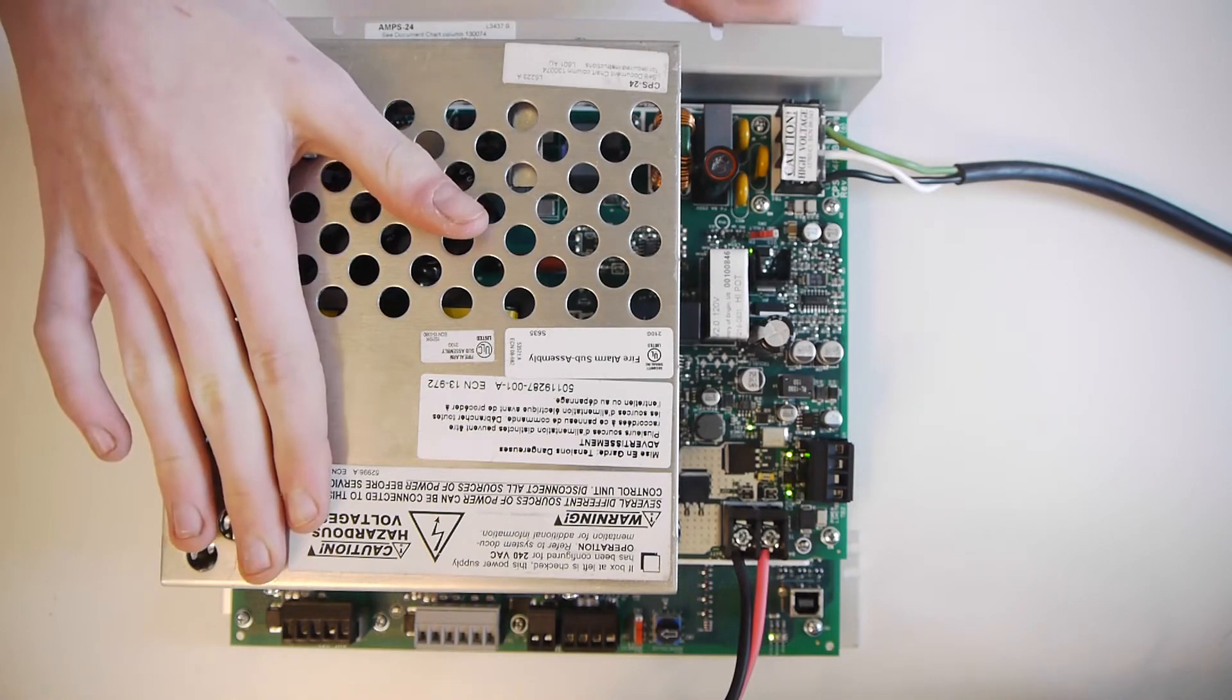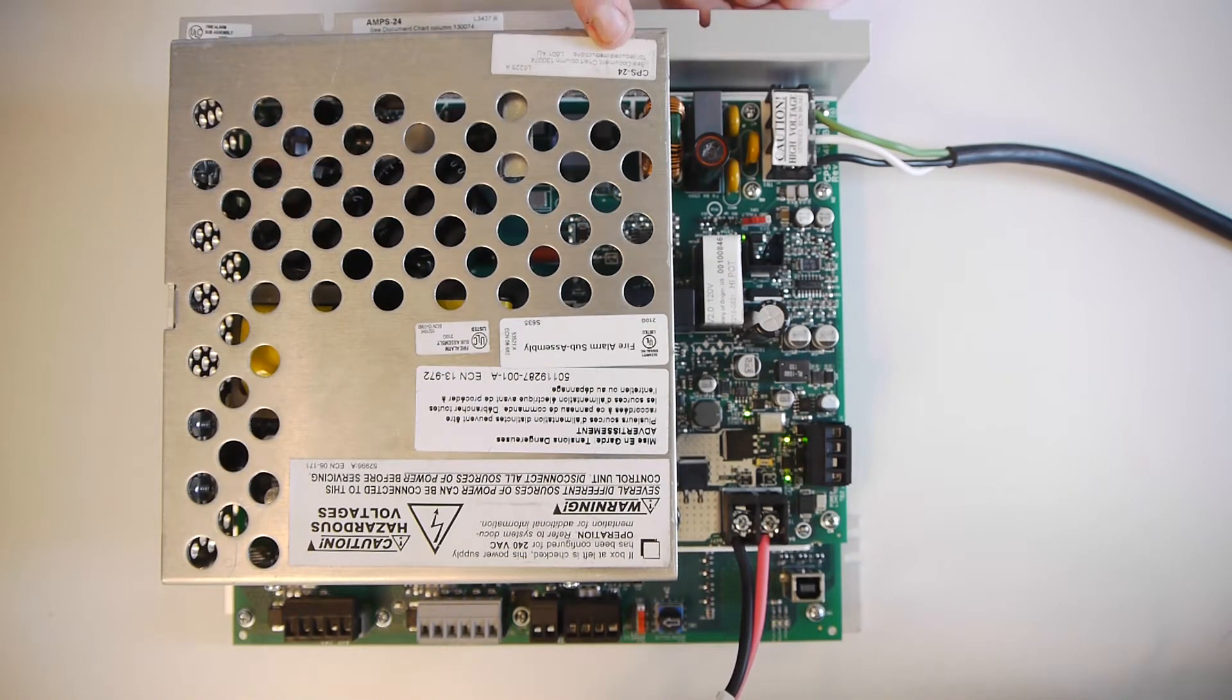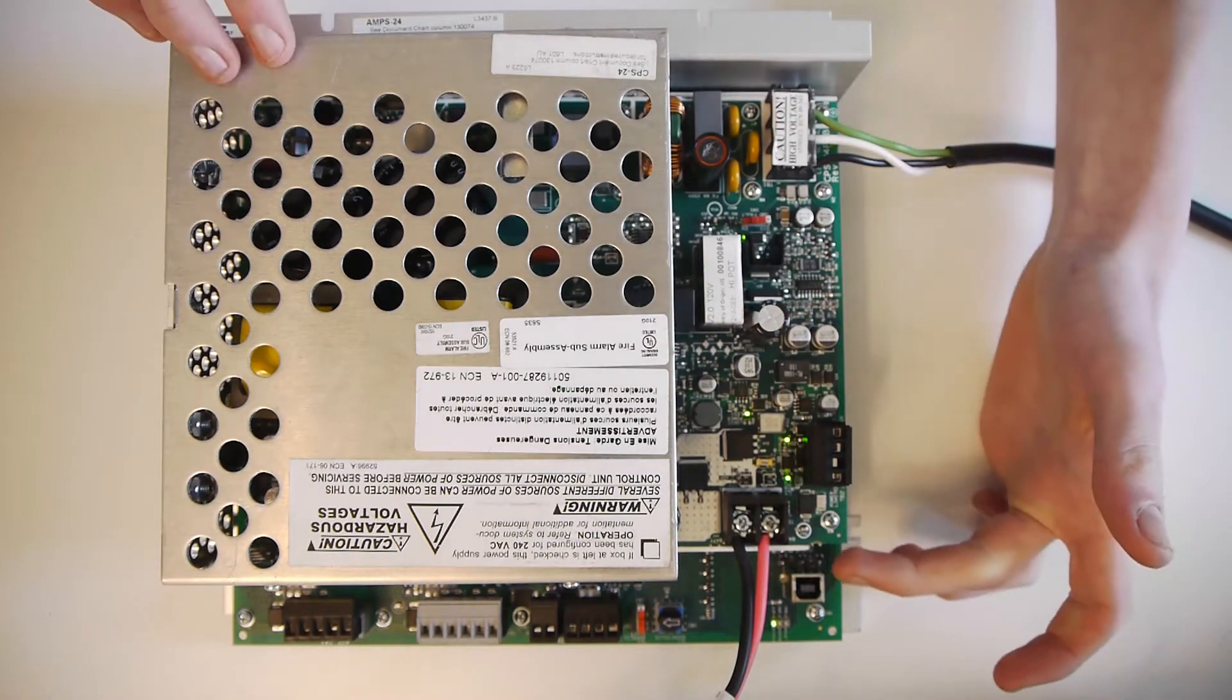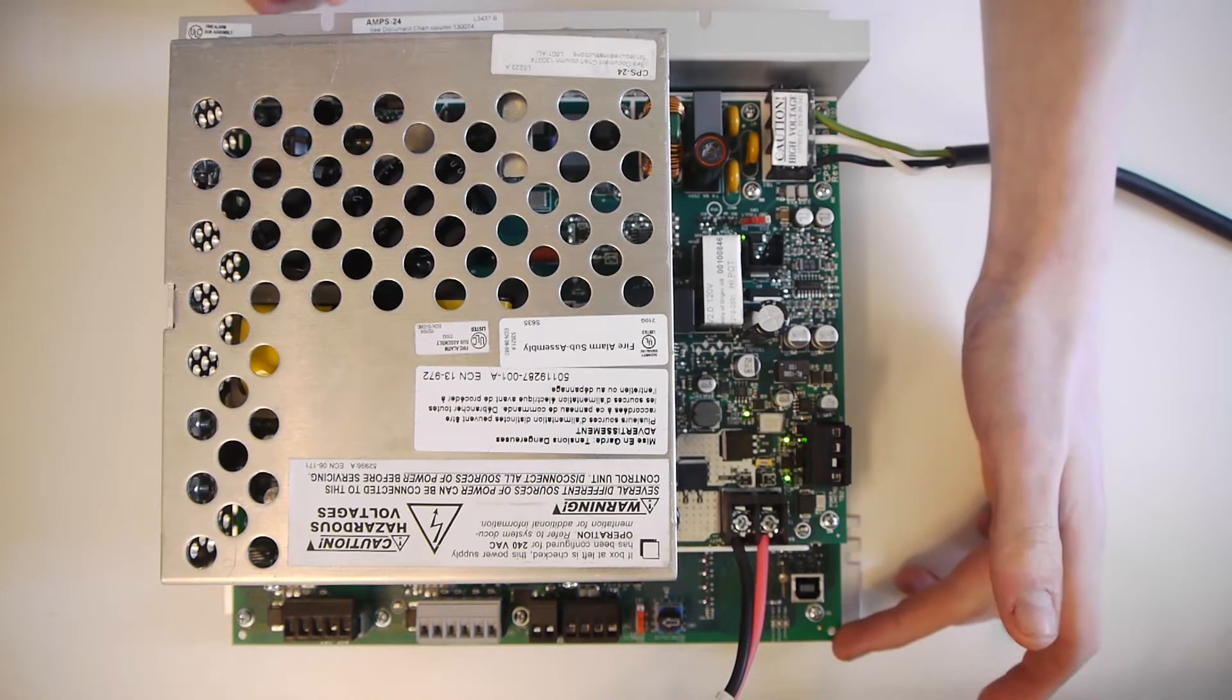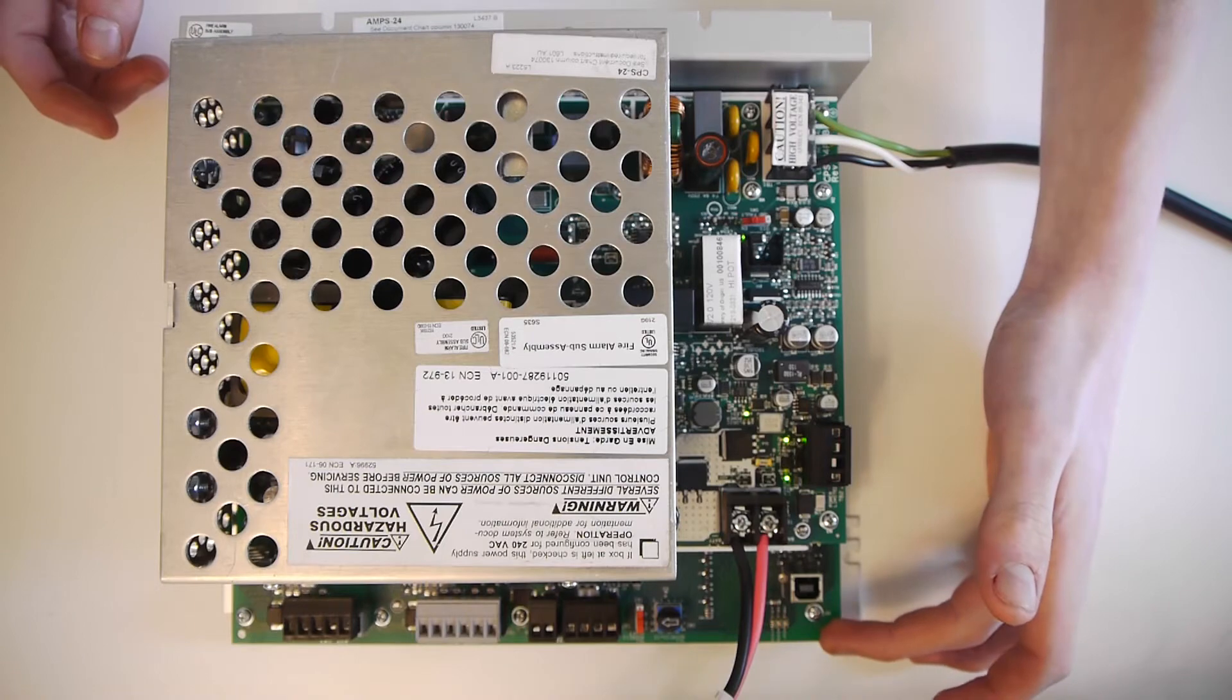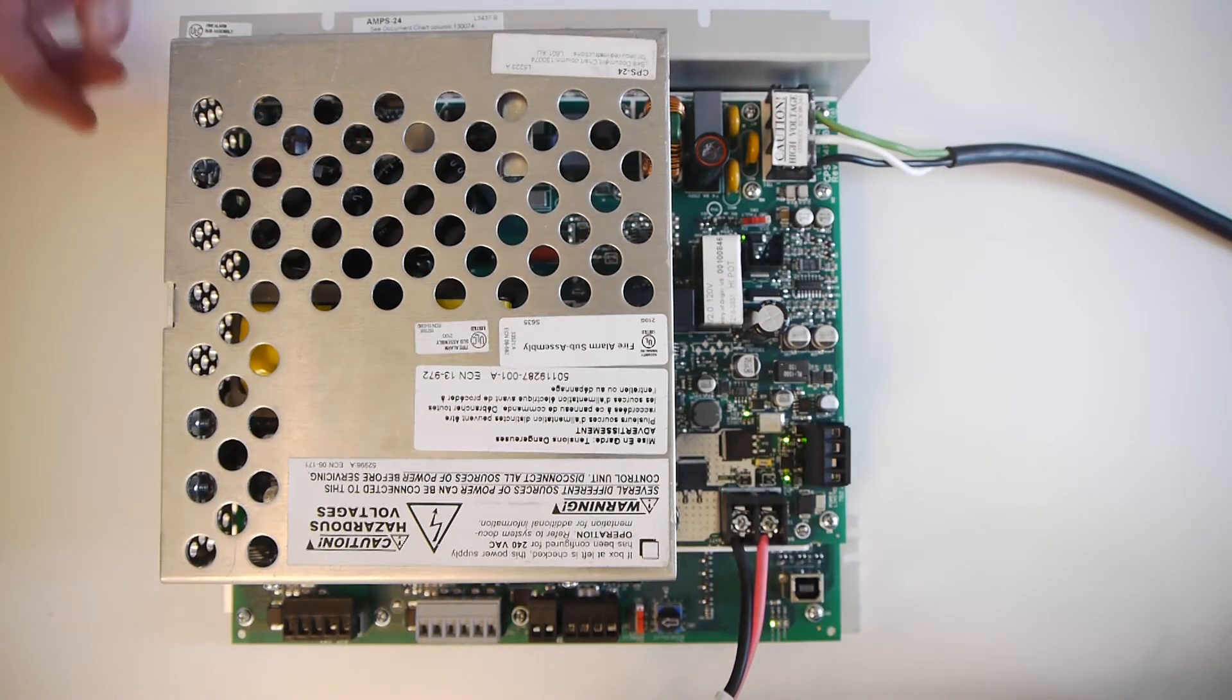Let's get started with explaining how this thing works. There are two main parts of this power supply. There's the Notifier CPS24, which is actually the power supply of this power supply, and it's the upper board. And there's the AMPS24-K2 board, which is the lower board. And this is kind of the I.O. board and intelligent part that communicates with the fire panel.